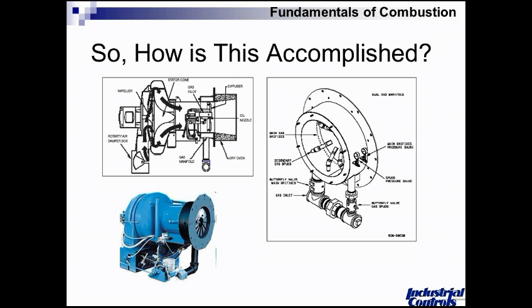What you end up with is really what looks to be a pretty lousy flame. But in reality, if you look at it with an analyzer, it's not so bad. Other burners have what visually appears to be a very good flame under most firing conditions, but you can be fooled. About the only thing I found, and this is really something that has to come from experience, is when you look at the very tip of the flame, if it's somewhat lazy, hazy, or smoky, you might have an issue, although I've seen some cases where that's not even true. So again, I would really encourage the use of the measuring tool, the analyzer. So now we know you did not crawl into that boiler to see what the flame looked like to judge if it was any good or not. No, I just was not thinking that day.